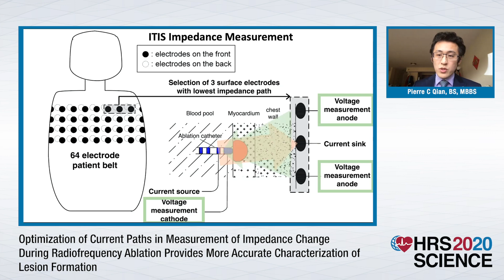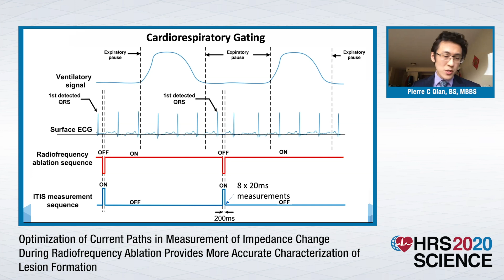While only 2 milliseconds was required for an impedance measurement, because environmental noise was unknown, 20 millisecond measurement intervals were used and 8 sets of measurements were performed for averaging. The system interfaces with the respirometer, ECG, electrode belt, RF return patch, ablation catheter, and RF generator. During ablation, RF energy passes through the impedance measuring system, which switches between ablation and measurement modes.